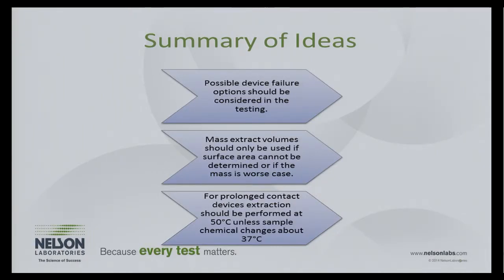Okay, this is one that once again we've seen happen, and the FDA is now putting it in this document, which is failure options. We have lots of devices that could fail during use. A balloon is the most common. A balloon that might have fluid running through it to blow it up, if that balloon bursts, now you have all the internal components that aren't intended to have patient contact, now would, because that fluid goes into the body. So you have to analyze your device and think of failure options of that device, and if it fails, would it expose portions of the device that normally would not be intended to be exposed?